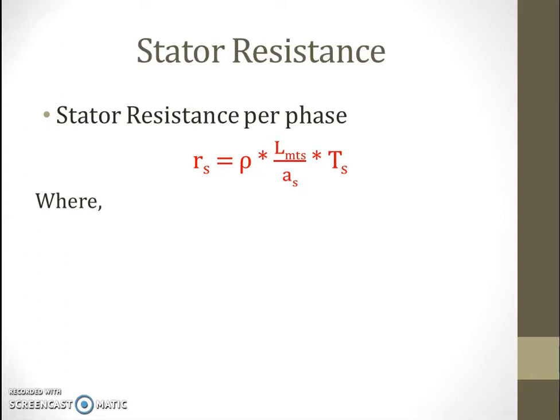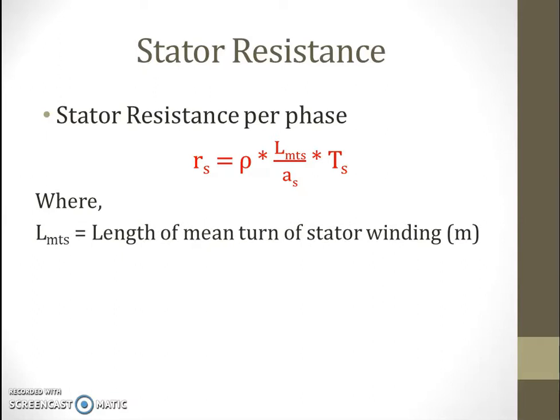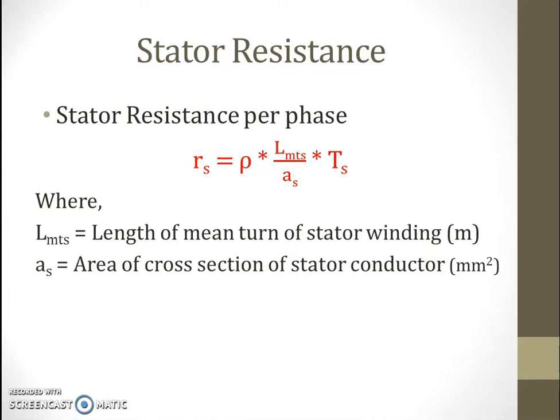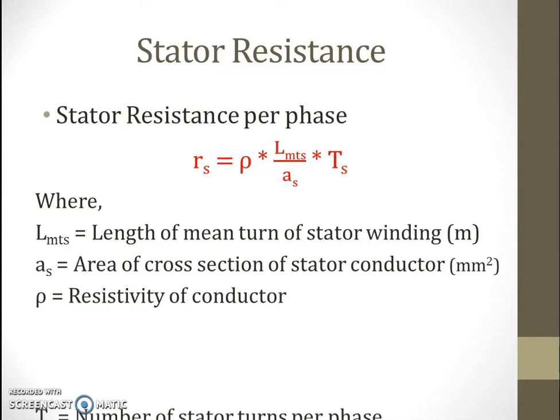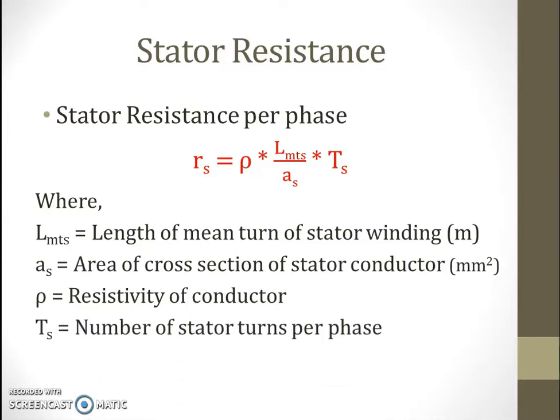As we give notations: Lmts — suffix S is for stator — is the length of mean turn of stator winding. As is the area of cross section of stator conductor. Rho is the resistivity of the conductor, which depends on the material used, and normally we use copper. Ts is the number of stator turns per phase.